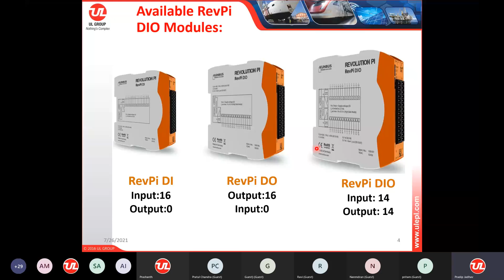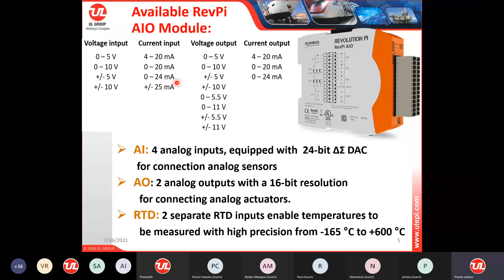Then we have the analog input output module, AIO. In AIO, you can select your signal type in the configuration software. The AIO has 4 analog inputs built in, 2 analog outputs, and 2 RTD channels to connect temperature sensors. This can be configured as a voltage or a current in a specified format. If it is current, it can be configured as 4 to 20 milliampere, 0 to 20 milliampere, 0 to 24 milliampere, plus 25 milliampere to minus 25 milliampere, like that. Same with the voltage as well.